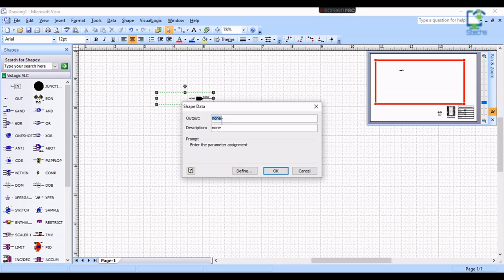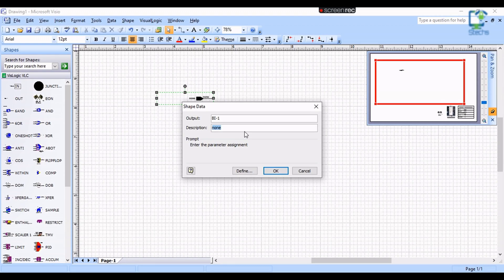A window opens named Shape Data. We must enter the input address in the output column of the block. If we are using a digital input on input 1, we must enter BI-1. The description I am giving is Status, or Fan Status.